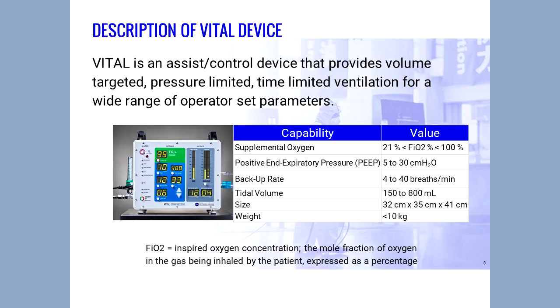I wanted to show some specifications of the ventilator. The ventilator is used to mix hospital-grade oxygen with ambient air, and you have to be able to fine-tune that ratio. These are some of the parameters. It has to be able to mix up to 100% pure oxygen. It has to have a specific positive end-expiratory pressure, which is an important parameter: the pressure as the patient exhales. The backup rate is also listed here. The tidal volume is the total volume delivered in one breath to the patient, and the size and weight of the ventilator is shown here.